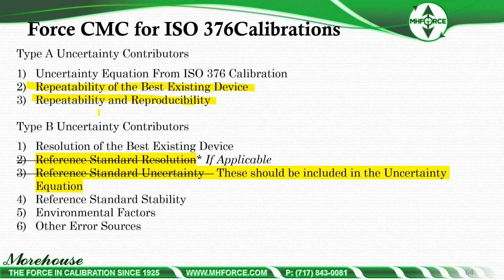But that's highly recommended for everybody to have stable artifacts in their facility. Whether you're doing ISO 376, E74, whatever you're doing, it's just going to help give that confidence, and it's going to help you with doing repeatability and reproducibility studies and quantifying that measurement process uncertainty if a similar device came in.